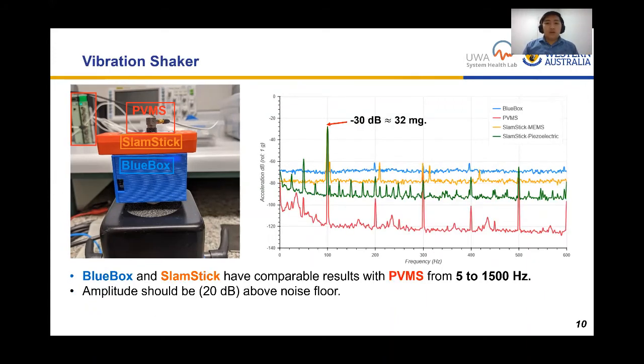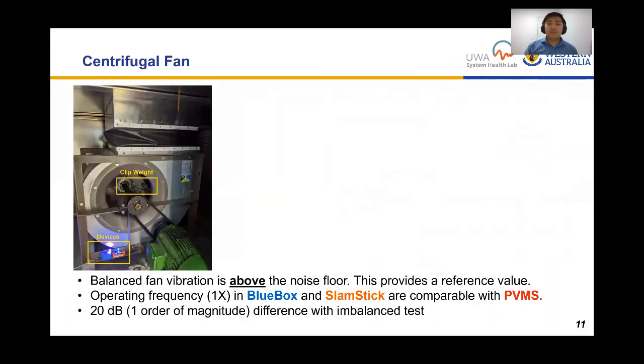The vibration shaker experiment with sinusoidal input shows we can detect the peak frequency of vibration. Tested from 5 to 1500 Hz, the 100 Hz result shows vibration amplitude at least an order of magnitude above the noise floor, which is important for distinguishing peaks even without averaging. This is a positive result — all devices, both MEMS and piezoelectric, produce comparable results in the vibration shaker experiment.